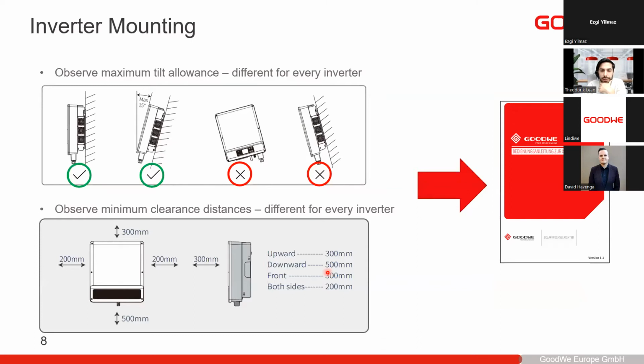Also, the direction that you can use for installing the inverter depends a little bit on the models. So please read the manual before you do this. In most cases, you need to install them standing up vertically on the wall. Do not tilt them in any way like this. In some cases, it is allowed to tilt them a little bit backwards, and then the maximum allowed tilt angle is 15 degrees backwards.